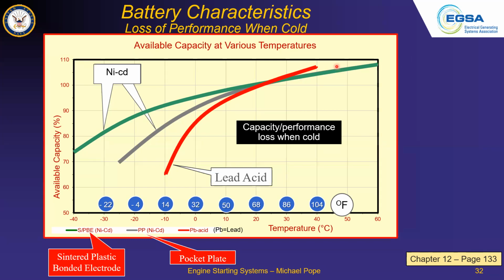I did a project for a military operation in Antarctica. The engine generator set had to be capable of starting on its own without attention during the winter months, and we had to prove it could be started at minus 45 degrees Celsius - that temperature doesn't make a difference whether it's Celsius or Fahrenheit. So we had to use a NiCad battery for that application. That's the effect of cold temperature.